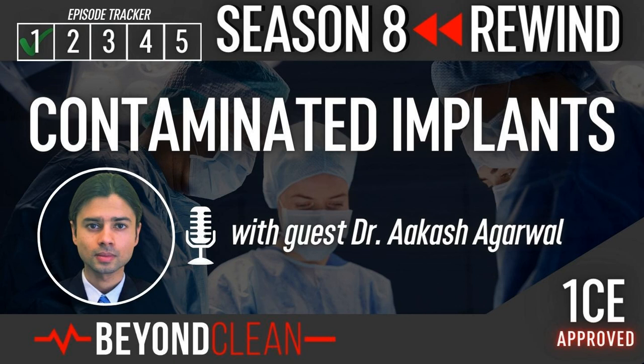So the problem with permanent medical devices in orthopedics is threefold when it comes to conventional reprocessing. One is the risk, the second is the reason, and the third is the responsibility. By risk, I mean the permanent medical devices in orthopedics have a lot of minute surface features, hidden or impermeable interfaces. These could be in sizes of millimeters or even less than a fraction of a millimeter. So naturally, reprocessing is very challenging and hard to truly validate in these devices. For example, how do you separate the components of the medical device to make sure nothing foreign is stuck in there? We don't really use a microscope on each and every device, and eventually it will be in the patient's body, so there is no room for uncertainty.